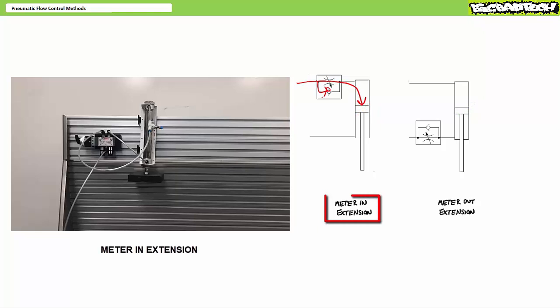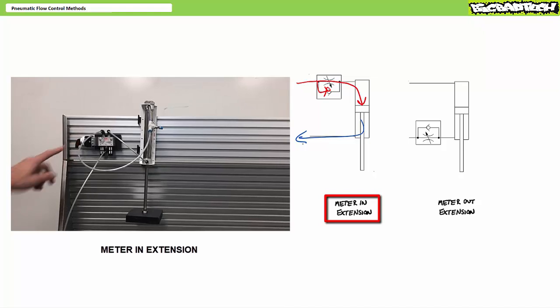A meter in extension does control flow entering the cap end, however with no restriction on the rod end. As soon as the rod end is exhausted to atmosphere, the load slams to the ground and breaks into a thousand tiny pieces. Let's try meter out.